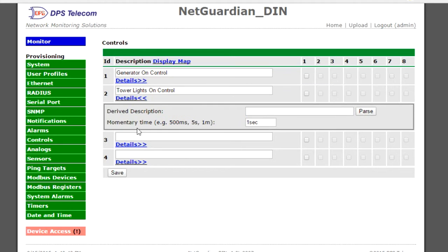So maybe you have a generator out and you want to monitor a certain point and then turn on a generator control. So it's kind of an automated process for you. So OR is like a logical operation. You have OR, NOT, and AND that we support. So you can use those to create an equation based on the alarms you need to monitor. If you just want to follow one alarm point, you would just do an OR and then the display point.